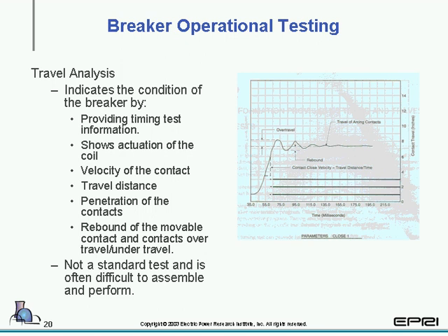The next item is we're going to look at a travel analyzer. Now, a travel analyzer is a good test, because not only does it perform the minimum pickup of the coils, it also shows you the speed at which the moving contact structure moves, and shows you ringing, as well as a graph that can tell you more information. And you actually see a little printout graph of a travel analyzer.